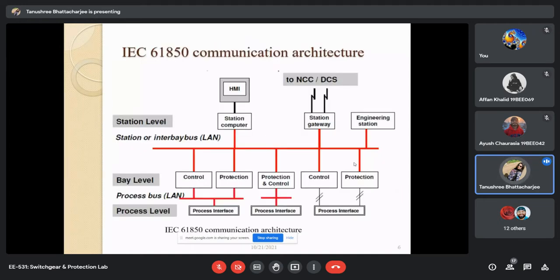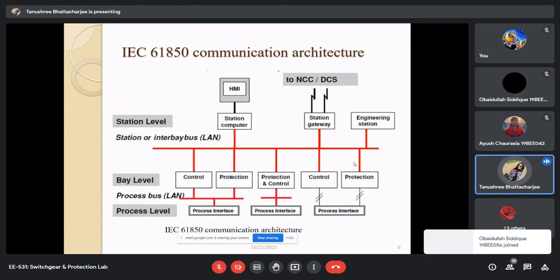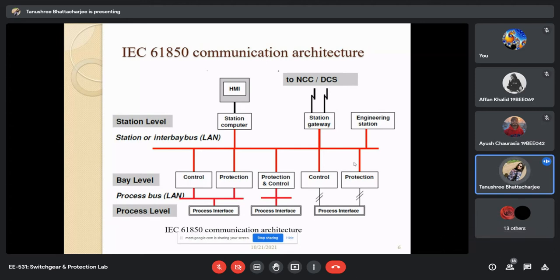Now this is the architecture. Considering a substation, there are three levels in the IEC 61850 communication standard: process level, bay level, and station level. Process level is the switchyard of a substation. Bay level is the control room of a substation, and station level is the monitoring part, which you can see in a power plant. Have any of you visited a power plant, like a thermal or hydro plant?